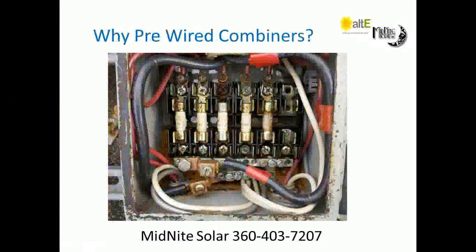Now, that wraps up inverters. Before I go on, I will talk a little bit more about AC coupled. I didn't spend a lot of time on AC coupled because the webinar was supposed to be solely on pre-wired. But with AC coupled, the question you have to ask is what kind of inverter is already there, because for the most part you want to consider it limited to a 1-to-1 ratio. So if you roll up on site and the customer has 3 strings of Enphase, 6 kW of Enphase, 2 kW per string, we'll say, and they want AC coupled, but they are on a budget. They want to do it as affordably as possible.